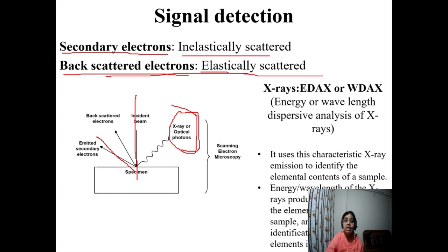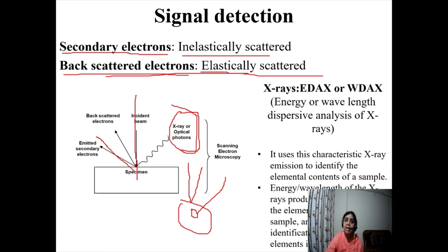Backscattered electrons are the incident electrons scattered by atoms in the specimen. Secondary electrons are ejected from atoms in the specimen. This is the basic difference: backscattered electrons are scattered by atoms, while secondary electrons are ejected from atoms. Secondary electrons are used for topographic analysis and backscattered electrons for compositional contrast. These are two very important signals in SEM machines.